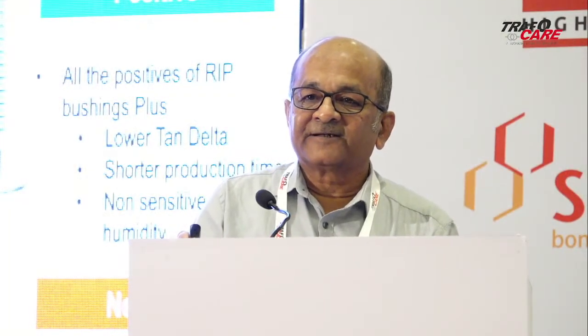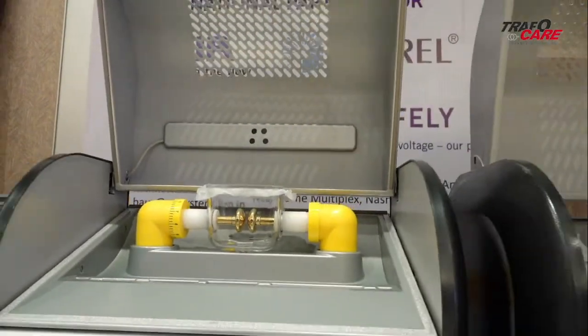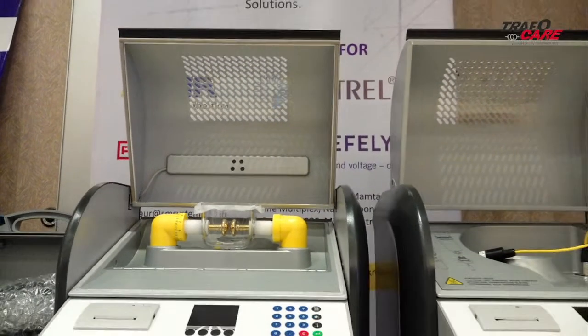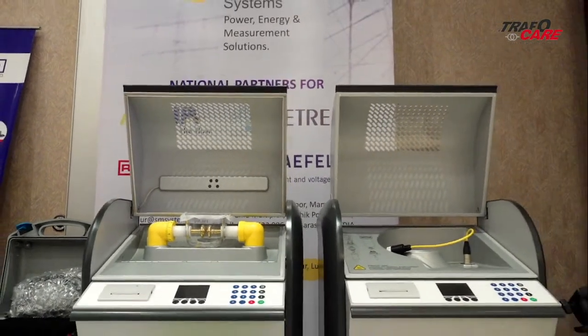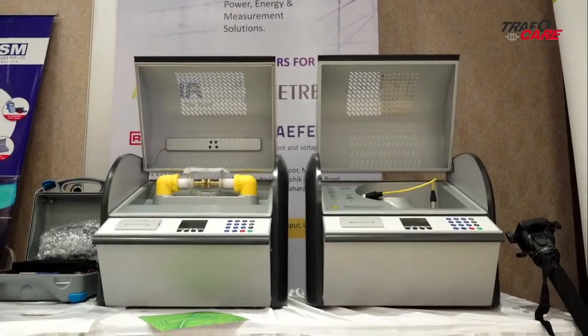The negative or constraining factor could be higher production costs, and because of resin impregnated paper, the bottom part is sensitive to moisture ingress if it is not stored well. Till the time it is mounted on the transformer, this is a sensitive aspect.